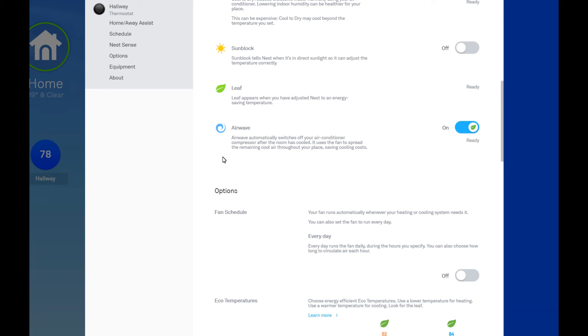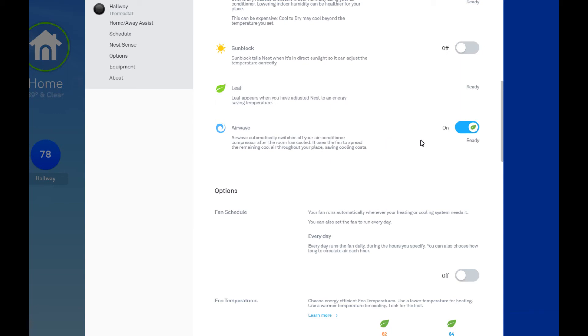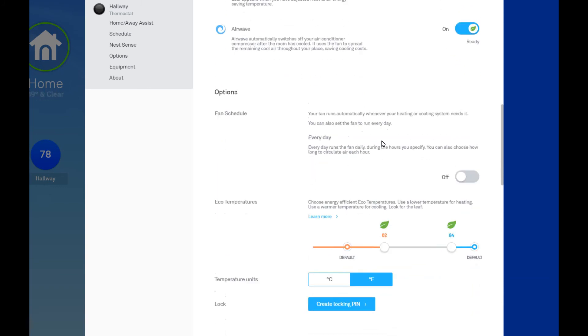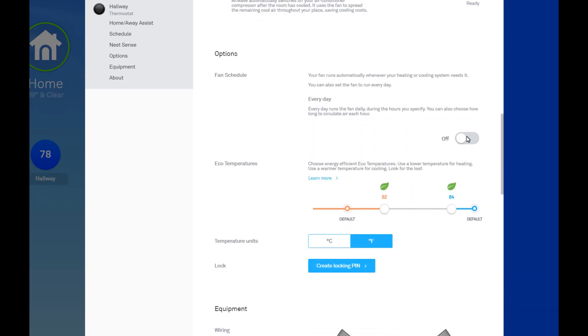So it kind of brings up the humidity a little bit, but that's not a big deal because it's 40% humidity in the house. So yeah, if you have this on, it will come on at, yeah, 40%. If it's below 40% humidity, airwave, that sequence will be enabled. It's not necessarily running, but if you're in cooling mode and it's below 40%, you might see this airwave logo on your thermostat. So that's a really good thing to have on.